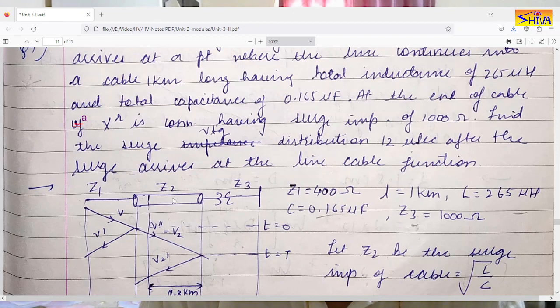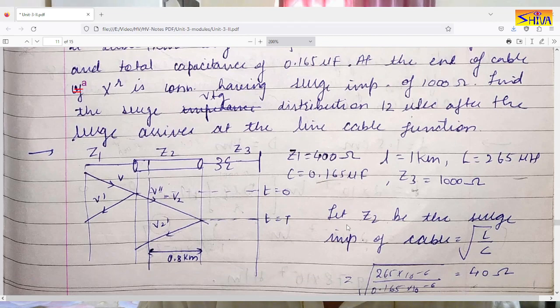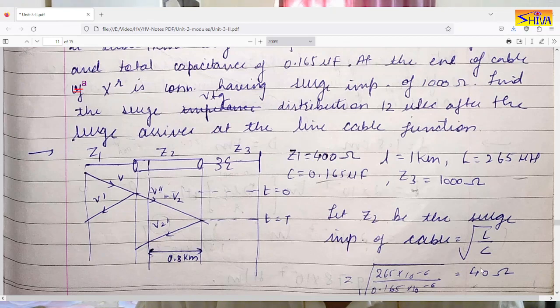The cable length is one kilometer, so inductance is 265 µH/km and capacitance is 0.165 µF/km. The surge impedance of the cable is √(L/C). Substituting the values, the surge impedance of the cable is 40 ohms. The surge impedance of the transformer is given as 1000 ohms.